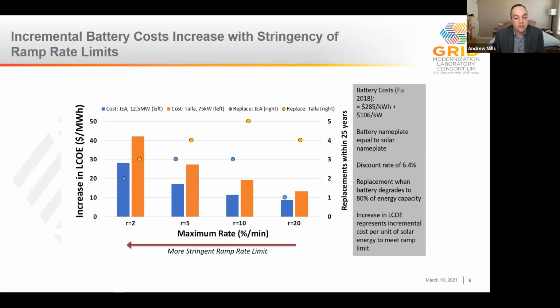Costs also increased with a more stringent ramp rate because the batteries had to be cycled much more often, and cycling can be costly since each cycle can degrade the battery and force its early retirement. Based on two utilities in Florida that we looked at, the additional cost of this ramp smoothing ranged from about $10 to about $40 a megawatt hour, depending on the degree of smoothing imposed.